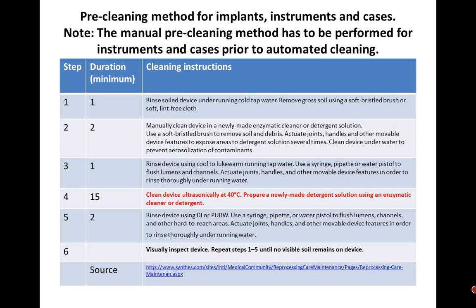So if you were ever surveyed and a surveyor asked you, why are you set at a certain time? You can say for these sets of instruments, it's 15 minutes. How? You refer back to the IFU. So we will touch on this later. There is no one standard time right now. It is based upon the instruments and the IFU. And this one is 15 minutes, not 5, not 10, but 15. And these are some very common instruments that are used in departments that have orthopedics.